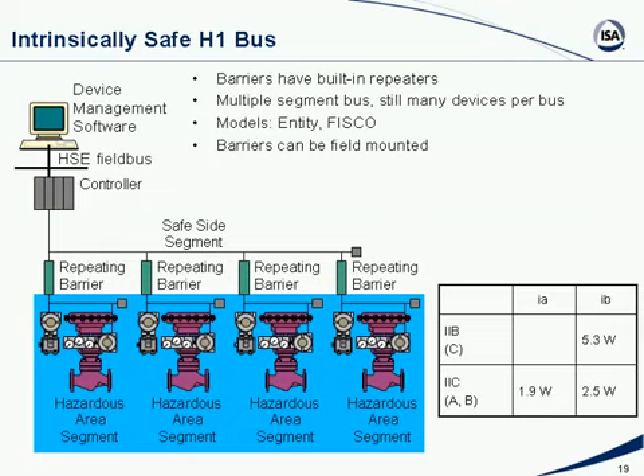Now, if we instead can use EEx ib design, we have 2.5 watts. So that allows me to put 8 devices per barrier. And if I can use gas group IIB, or C, as you call it in North America, I have as much as 5.3 watts of power available. So then I can connect no less than 13 devices on one barrier. And that's about all you would really need, okay?